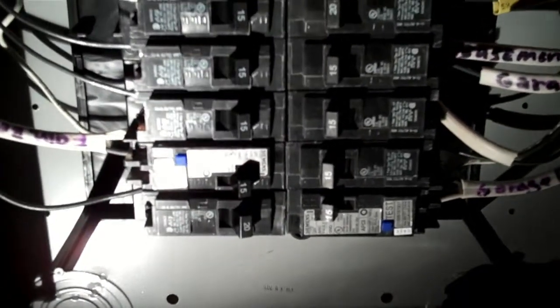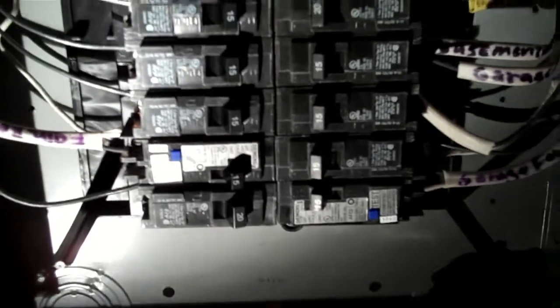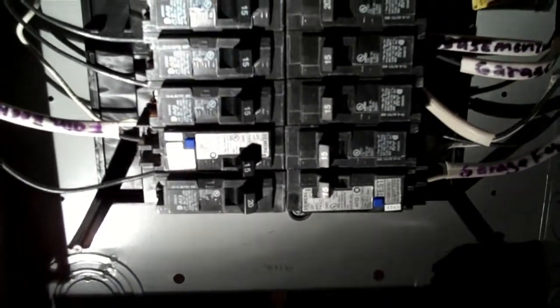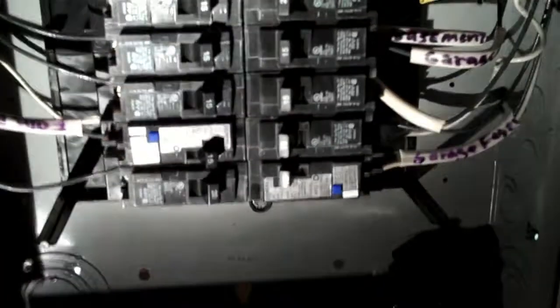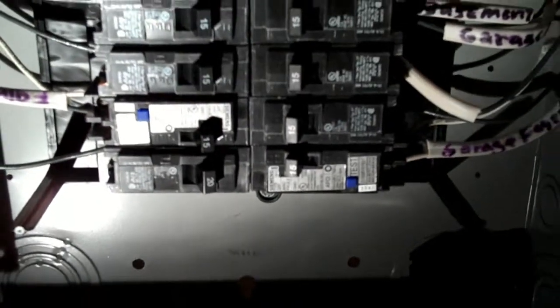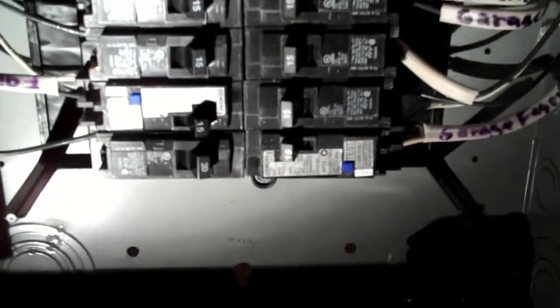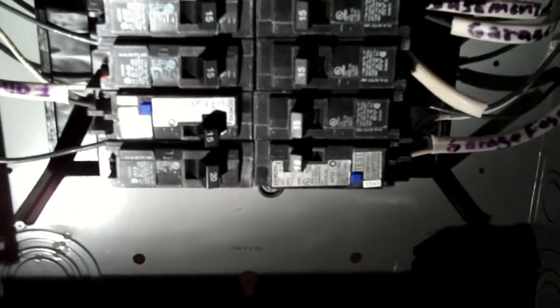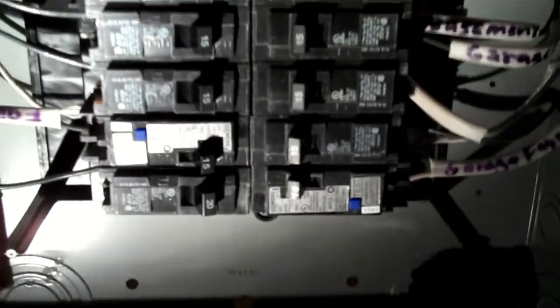So not to get too technical, but there should be arc fault circuit breakers installed for just about every room on new construction. And as you can see here, there's only two. And what's even more strange is that the arc fault here is for a family room and a foyer area. So there's no arc fault protection on any of the other rooms, including the bedrooms.